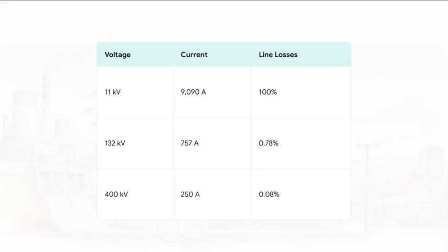Let me put this into perspective, because the contrast in efficiency is awe-inspiring. Imagine we tried to transmit a 100 megawatt load at our starting generation voltage of 11 kilovolts. We'd have to push over 9,000 amps of current. The heat losses would be absolutely catastrophic, the cables might just melt. But when we use a step-up transformer to boost that voltage to 400 kilovolts, the current plummets down to just 250 amps. And those line losses drop to a microscopic 0.08%.